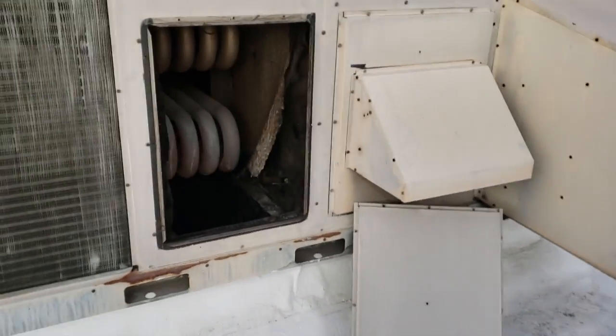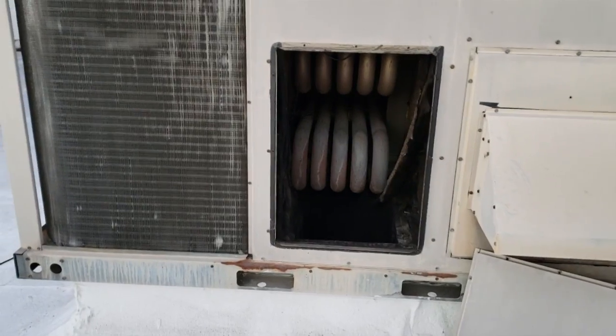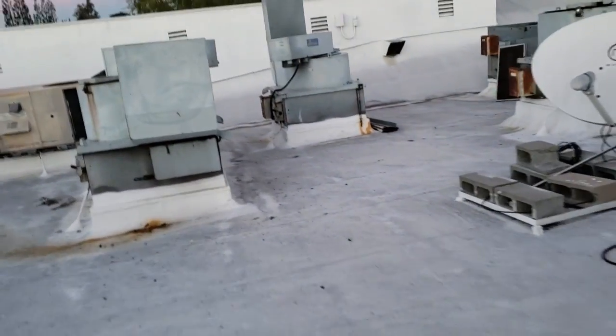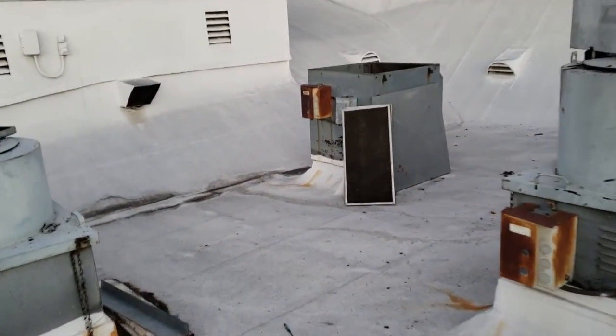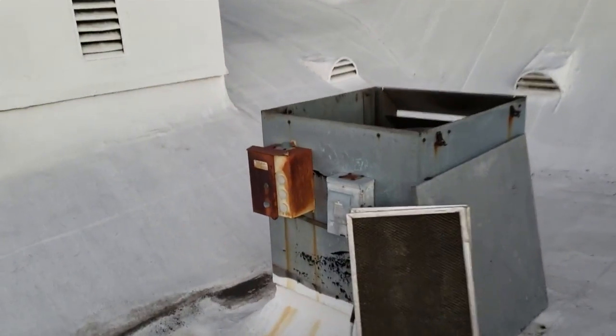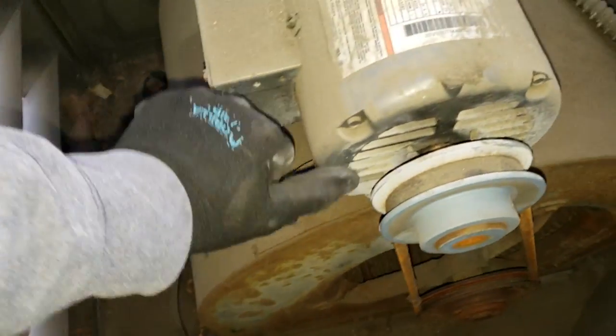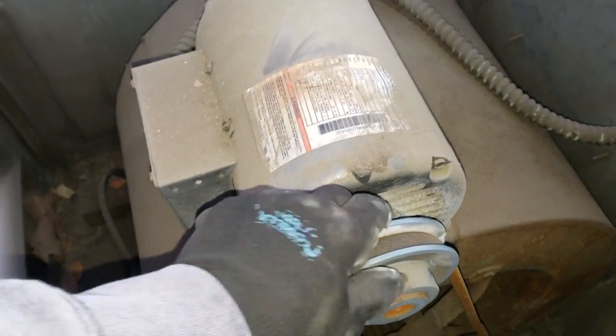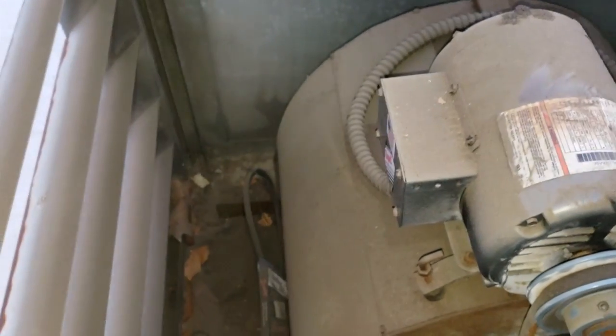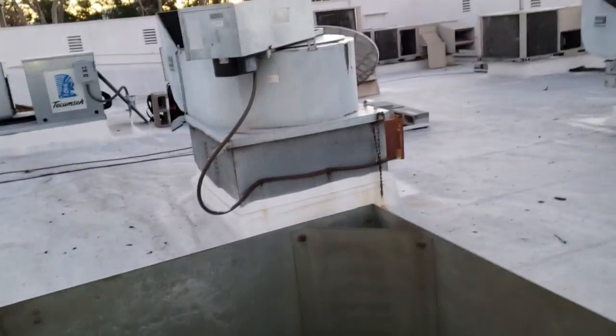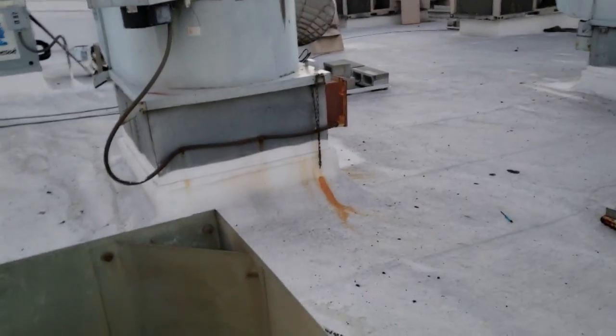The cook downstairs doesn't really know, but I'm just looking around. I went ahead and turned on all their exhaust fans, and I checked out the makeup air units too, and I noticed that this makeup air unit was shut off. It doesn't smell burnt, but there's a bunch of white powder all over the place. So I have a feeling that this motor is bad and it was smoking, and my theory is that it was blown into the kitchen and the smoke was getting sucked throughout the dining room. That's my theory. I don't know if that's the case yet.